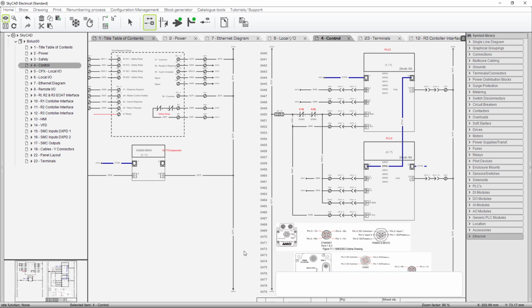And the whole idea of a lot of what I did here is to reduce the challenges of commissioning a machine in one state, tearing it down, shipping it to another state, and reassembling it and recommissioning it. So the more cables with connectors that are properly marked you use, the less fooling around you have to do in junction boxes, especially when you have wires that the numbers have fallen off, or maybe they didn't mark them at all. So what we have here is, this is a cable.